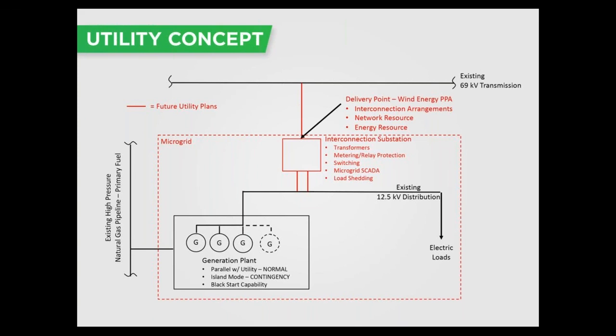Our interconnection substation there, where we have our transformers, we'll have our switching, cutouts, and those types of things that will allow that generating plant, which is going to be sized adequately enough to take care of the whole microgrid. We will island off from that point of coupling and be able to island indeterminately. Since I have natural gas supply, I can island off for days or weeks if I need to from the grid itself.